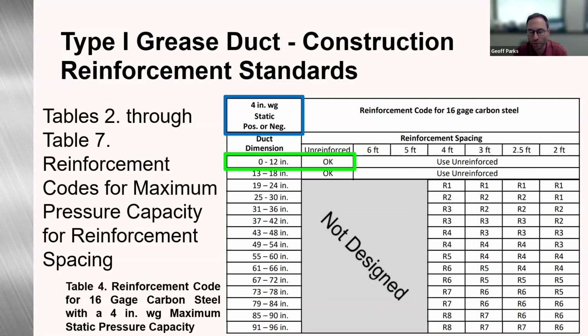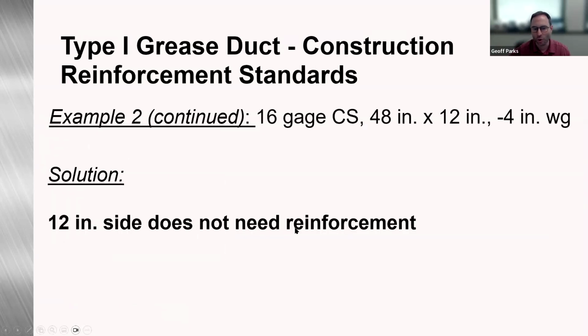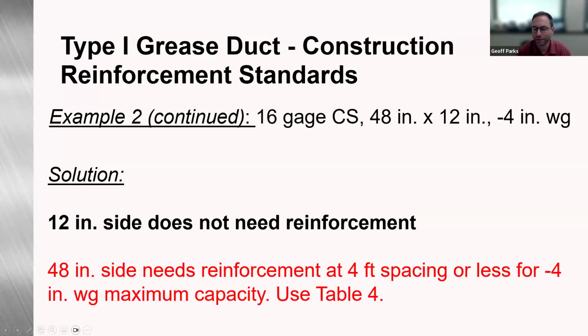So now that we know, hey, we need something every 4 feet for that 4-foot side, table 2 through table 7, these are your reinforcement code requirements at the maximum pressure capacity for the reinforcement spacing that we selected. These tables have really, really long names. I apologize for that. But if we went to table 4, so this is the 4-inch static pressure table, looking at the 12-inch side of that 48 by 12, what this is telling us is we're okay. We don't need any additional reinforcements. They can be unreinforced. So the 12-inch side does not need reinforcement. Again, the 48-inch side does need reinforcement. And we picked 4-foot spacing, and that gave us our 4-inch water gauge capacity.